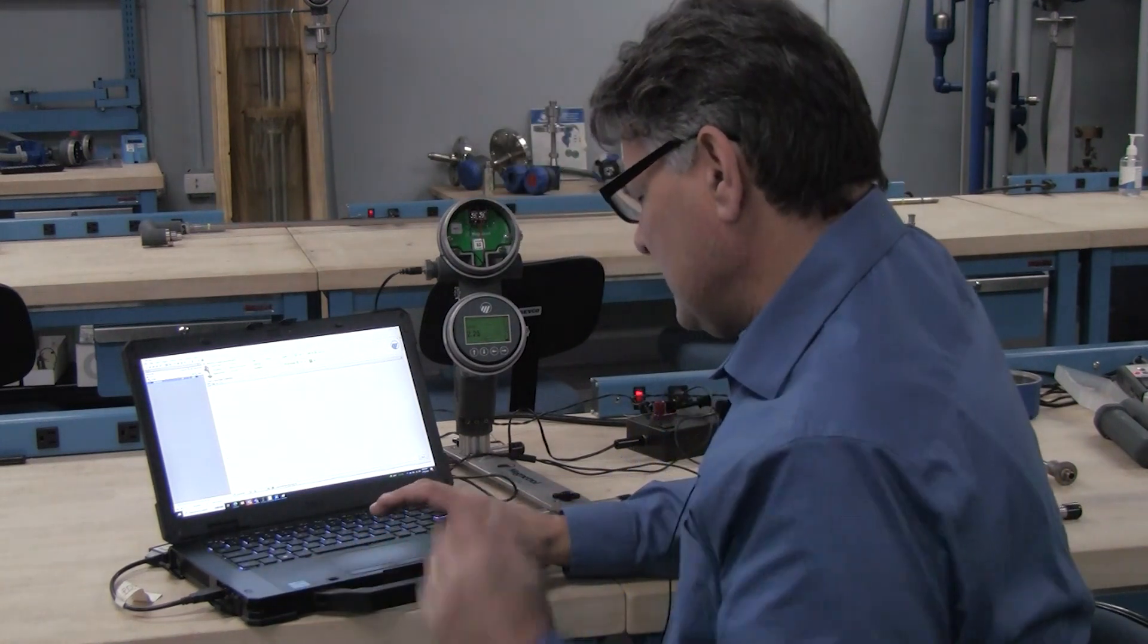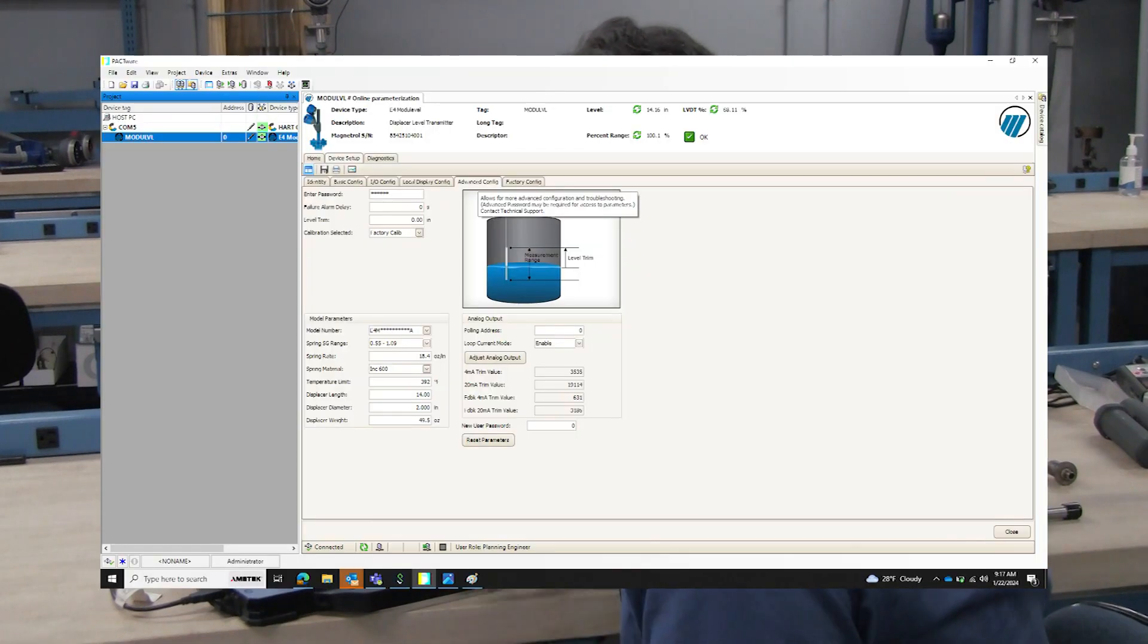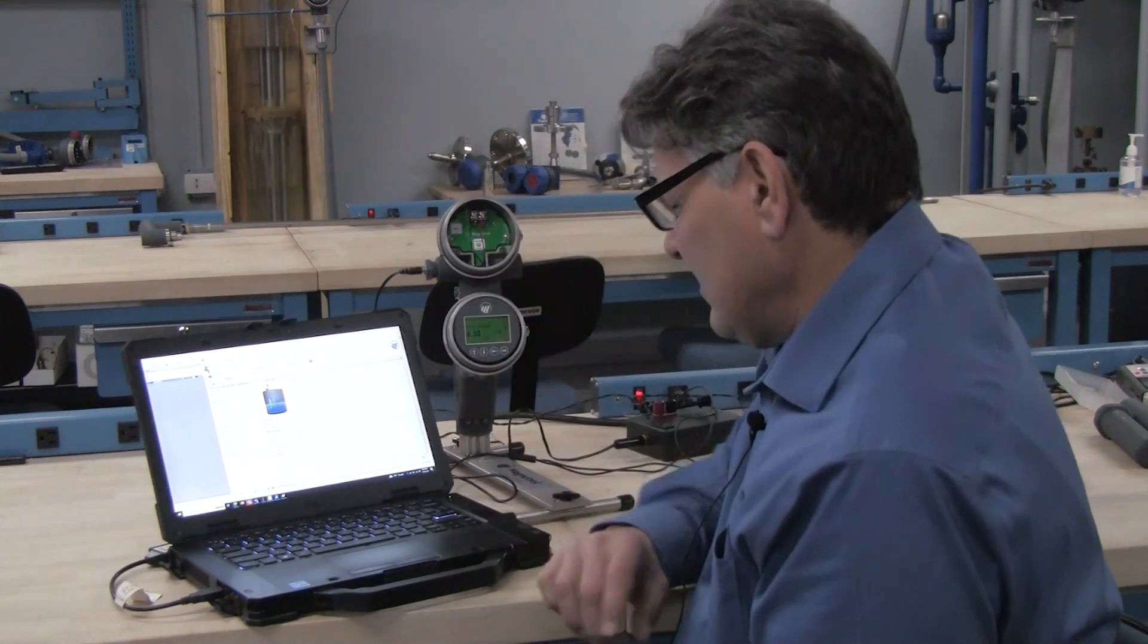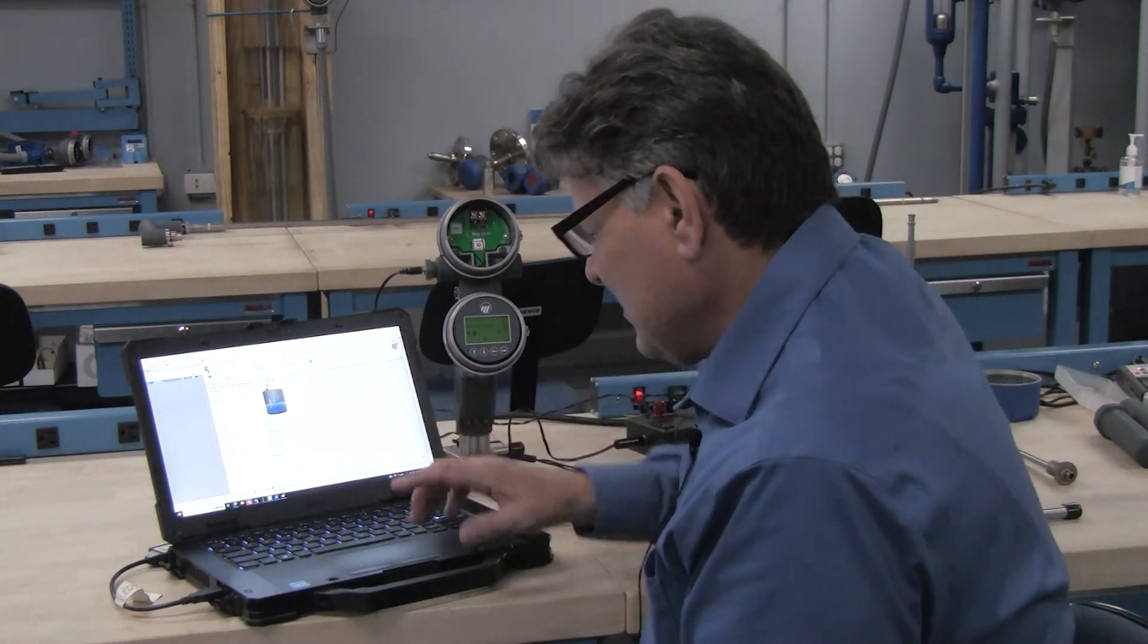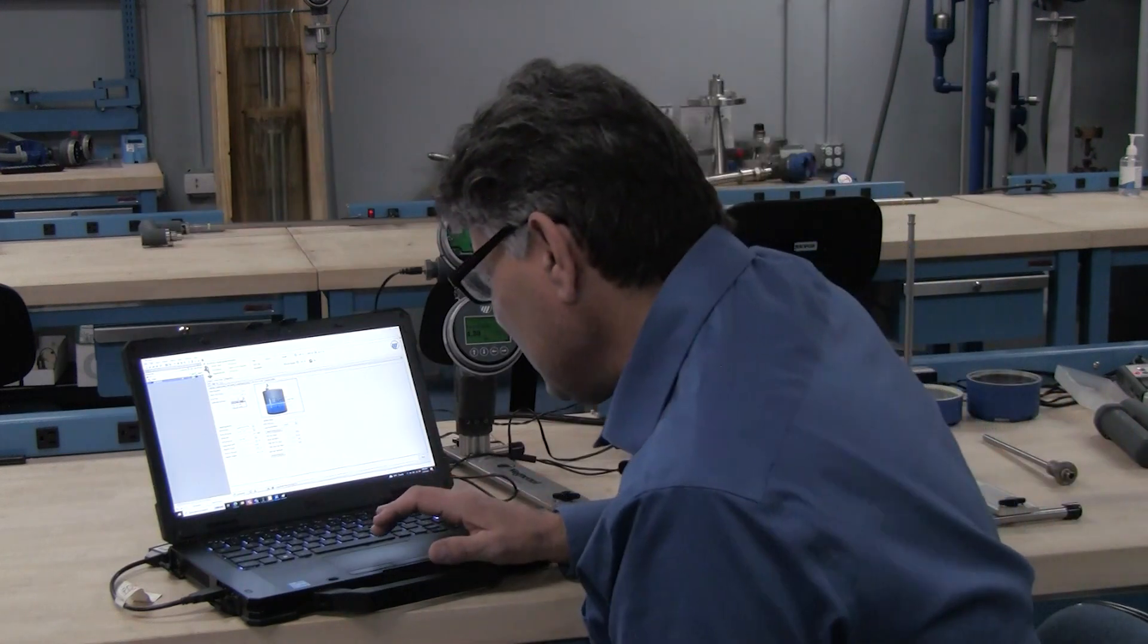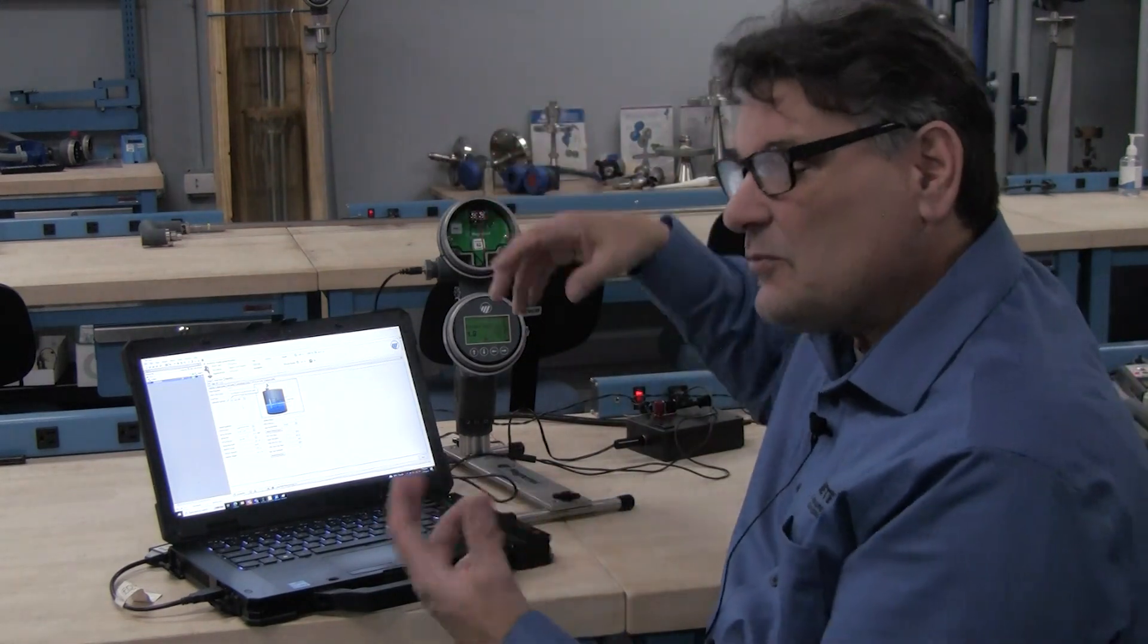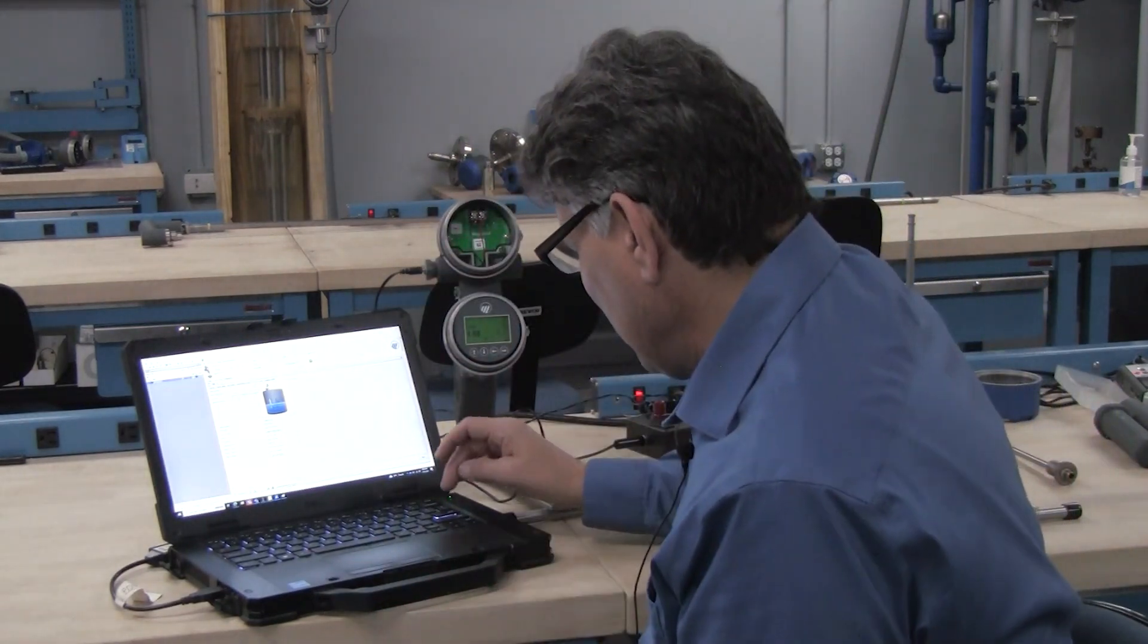I go into device setup, advanced configuration, I'm going to enter password 126 in the enter password line, enter 126. I'm going to go to calibration selection, right now it's in the factory calibration, I'm going to go ahead and change it to a user wet calibration. Because with the test stand, I'm simulating the core movement as if it was wet.